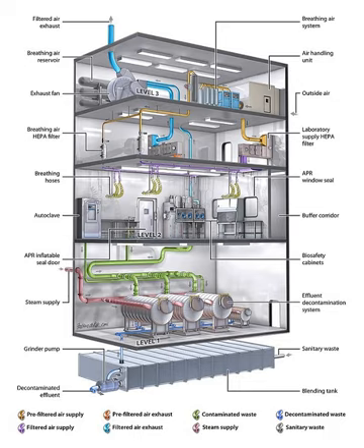The laboratory must be behind two sets of self-closing doors to reduce the risk of aerosols escaping. The construction of the laboratory is such that it can be easily cleaned. Carpets are not permitted, and any seams in the floors, walls, and ceilings are sealed to allow for easy cleaning and decontamination. Additionally, windows must be sealed, and a ventilation system installed which forces air to flow from the clean areas of the lab to the areas where infectious agents are handled. Air from the laboratory must be filtered before it can be recirculated.